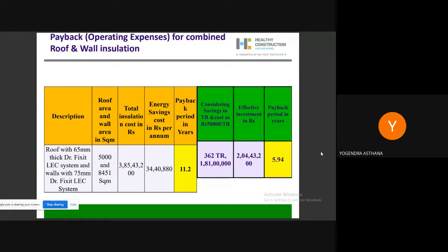But if we check how much ton rating we have reduced, the ton rating is the initial installation demand of our cooling system. So there we saved 362 ton. We are cooling this structure with a smaller refrigeration tonnage. So here we have saved 1 crore 81 lakhs rupees in ton rating. By virtue of this, we will recover our amount in 5 or almost 6 years. So this is how insulation is not an expenditure, it is an investment. So next slide, please.